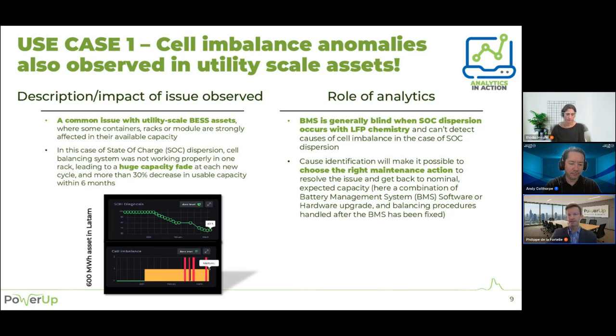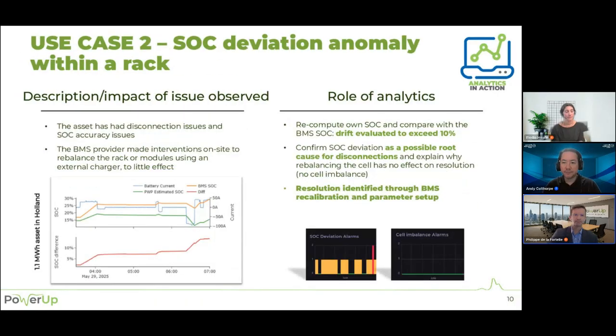Hey Elodie, let's move to the second use case on our list. Yeah, so after cell imbalance, let's talk about SOC deviation. The accuracy of the state of charge is an important matter for users, because they want to make the most of their systems. If the SOC isn't right, they won't use the system as much as they could. Today, in a BESS, the SOC is calculated by the BMS, the battery management system, from measurements of voltage, current, and temperature.